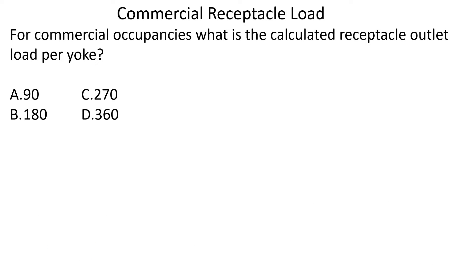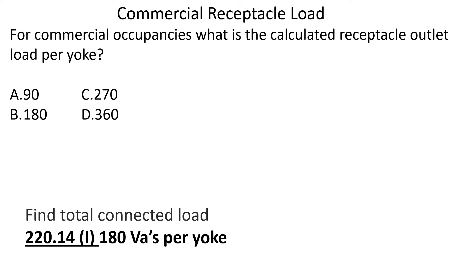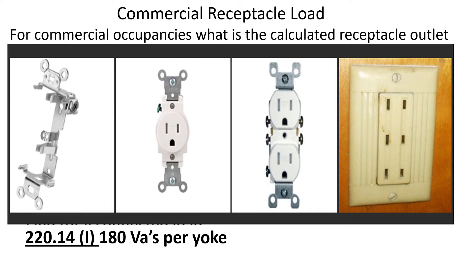For commercial occupancies, what is the calculated receptacle outlet load per yoke? First, we find our total connected load. We head to 220.14I, which tells us it's 180 VAs per yoke. But what is a yoke? A yoke — also called a device strap — is what holds all the pieces together. Whether we have a single, a duplex, or even a triplex receptacle, each one counts as 180 VAs. Each gang counts as 180 VAs: a single-gang box is 180 VAs; a two-gang box with receptacles on each side is 180 VAs per gang, and so on. Any device strap, whether it has one, two, or three receptacles on it, is 180 VAs per yoke.